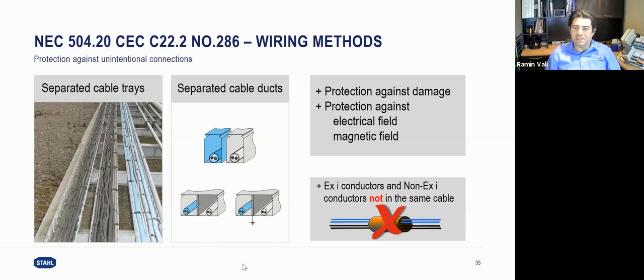So there are 2 considerations here. One is the interference, the electromagnetic field from the high power, and the other one is protection against damage, because if you have damage, high power may be connected or short-circuited to the intrinsically safe wire, and that will eliminate the intrinsically safe loop situation.